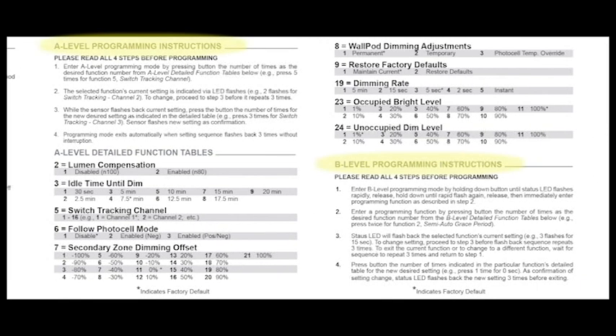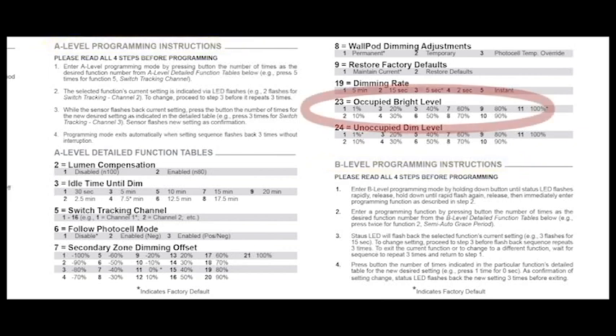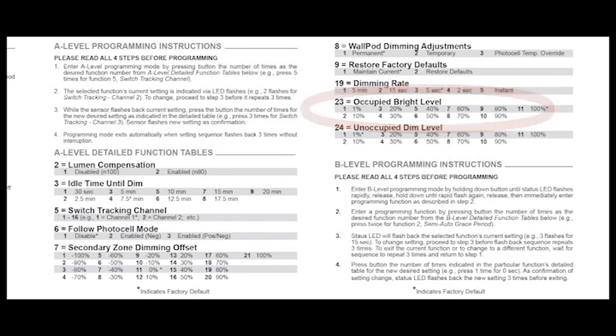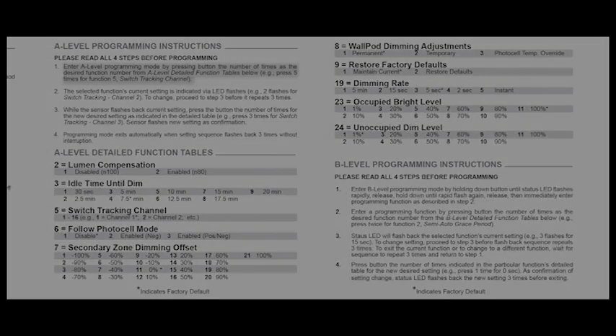Let's start by changing the Occupied Bright Level function, which will control the max level of light whenever occupancy is detected or a luminaire is overridden on. The Occupied Bright Level is housed under the A-level programming and refers to number 23. To enter the A-level programming, simply press the programming button the number of times that corresponds to the function. In this case, it will be 23.